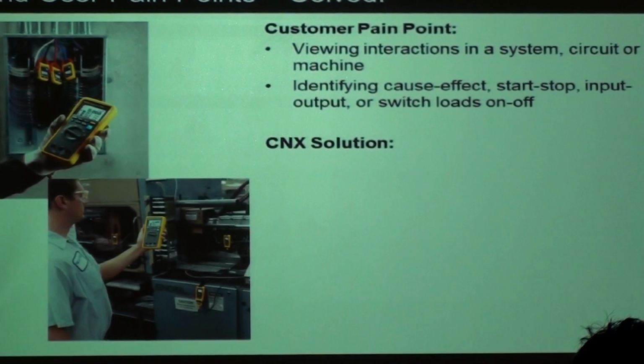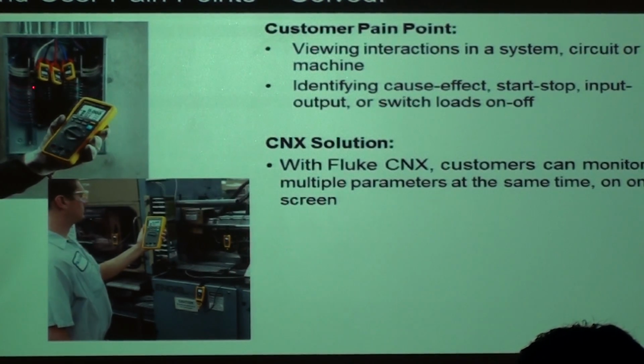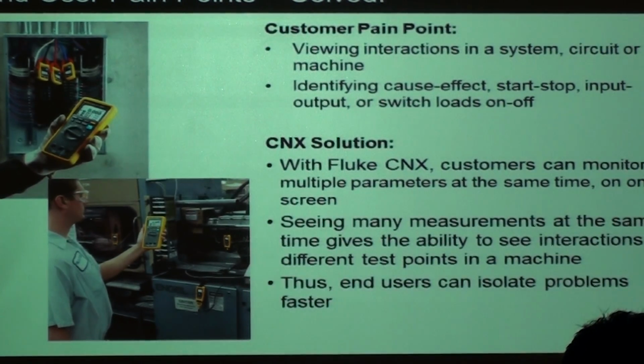So it's basically remote, simultaneous, and recordable. In an issue where sometimes you need to measure interactions in the system, start-stop conditions, quick on and off systems, switching loads on and off, I can use the CNX. So like here, three-phase, or here I want to measure the voltage, current and temperature at the same time. Like on an HVAC system, I can do that simultaneously to make measurements wirelessly. And it works from a distance of 20 meters, so you don't have to worry about space issues. You can be really far away from the device.